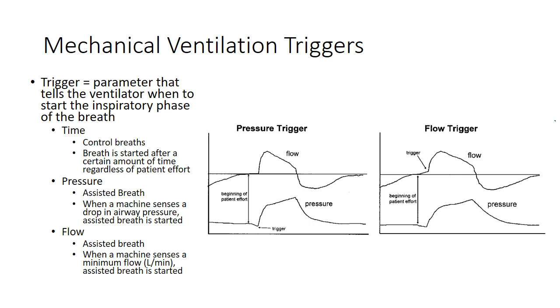Flow triggers are very much the same, except instead of sensing a change in pressure within the circuit, the machine will sense a change in flow in the circuit. This is usually measured in liters per minute. Whenever the trigger is reached, the machine will then give a set amount of support to the breath.